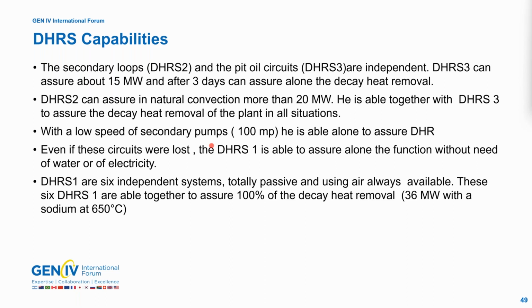So we have made a lot of calculations of the DHRS capabilities to validate the proposition. The calculations show that the secondary loops and the pit oil circuits can assure the decay heat removal, and after 3 days can assure it alone. The secondary loops can assure more than 20 megawatts in natural convection, and together with the DHRS3 are able to assure the decay heat removal alone. With the low speed of the secondary pumps, the DHRS2 is able to assure the decay heat removal alone.